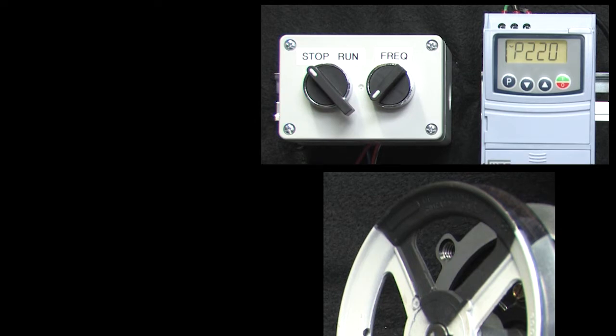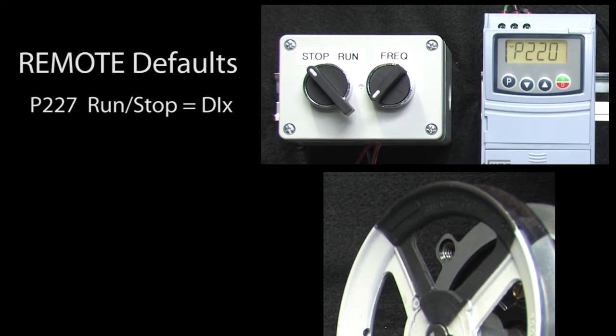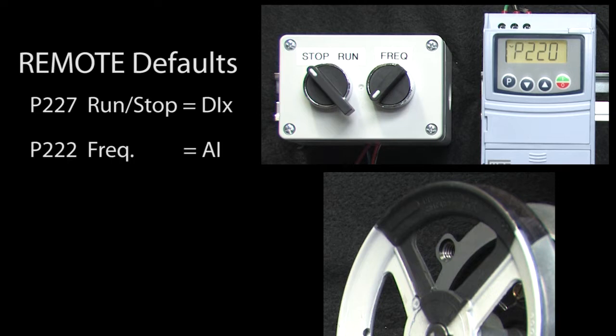Why is that? Well, because the remote configuration defaults to run-stop being controlled by a digital input, not the drive's HMI keypad. And the reference frequency defaults to being controlled by an analog input – again, not the drive's built-in HMI keypad.